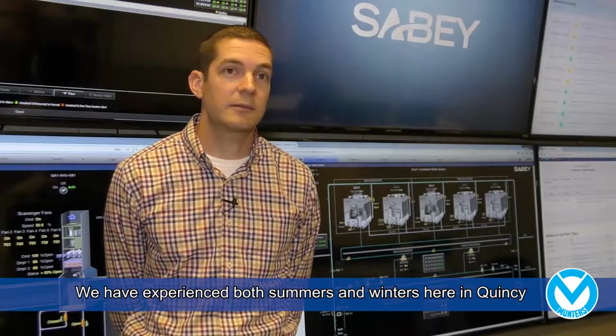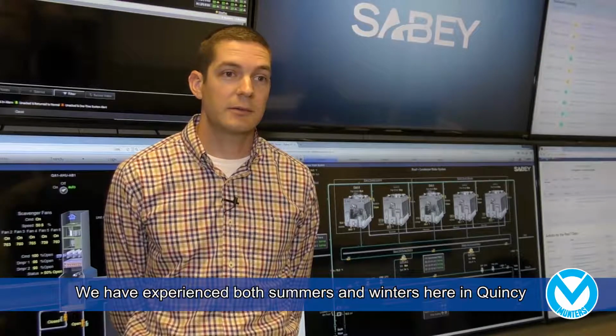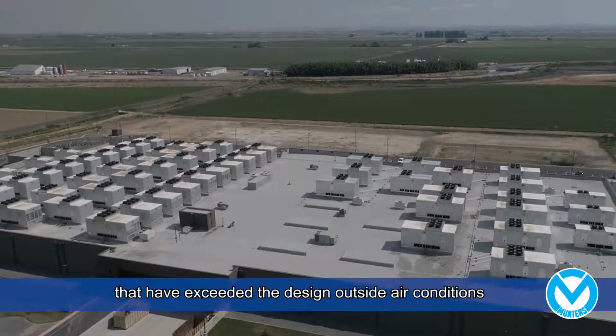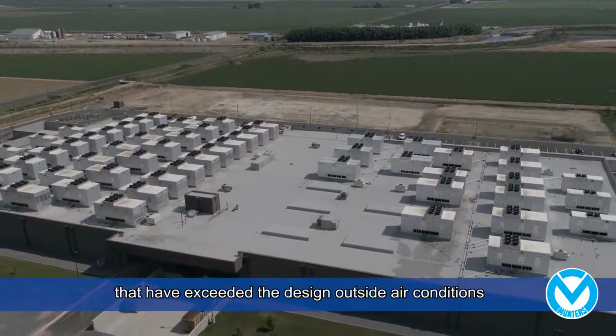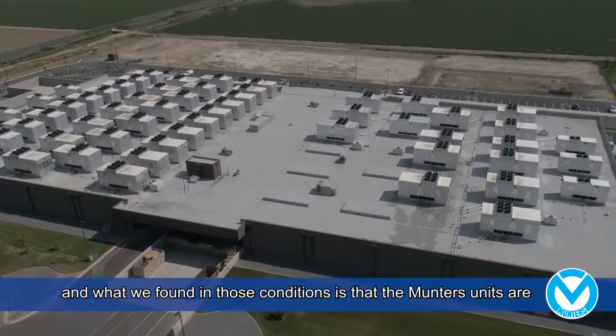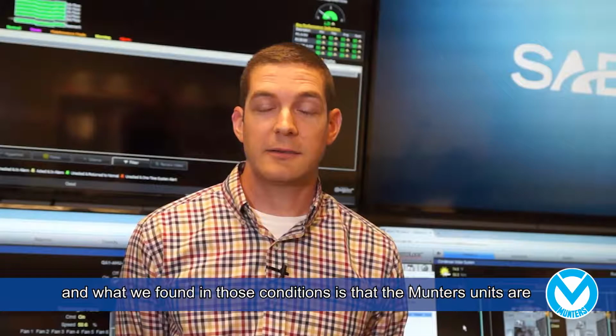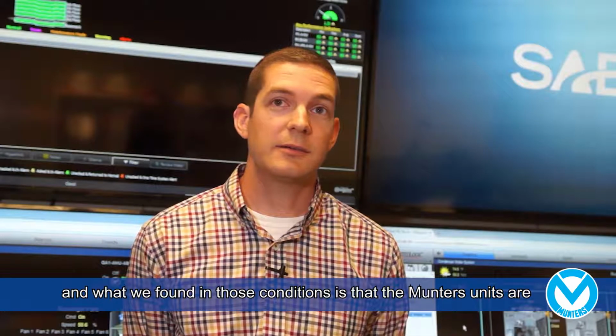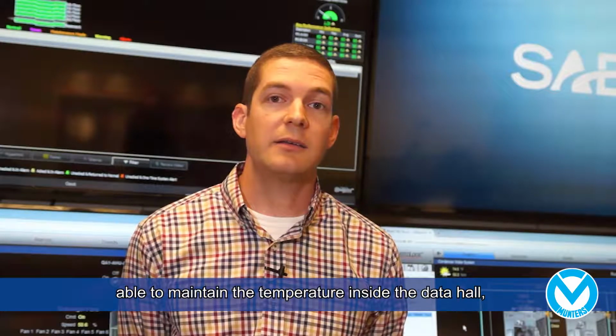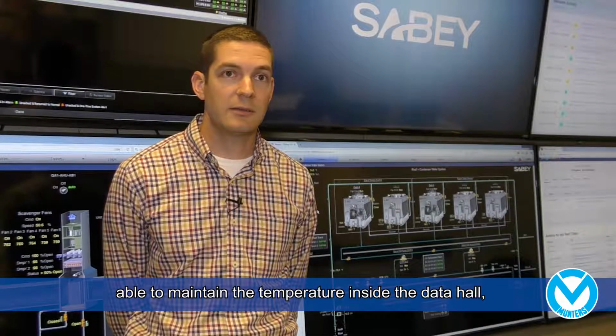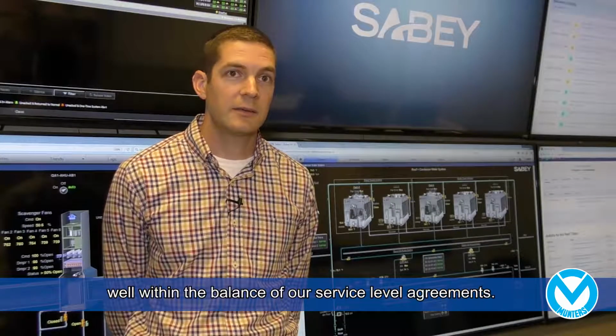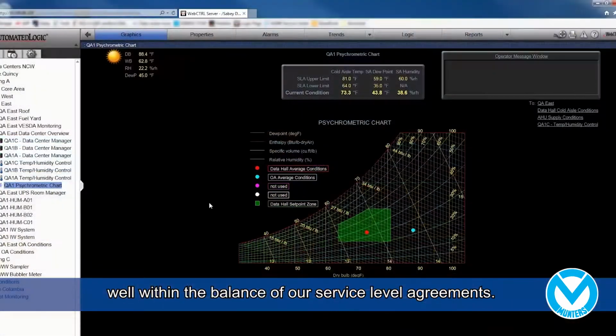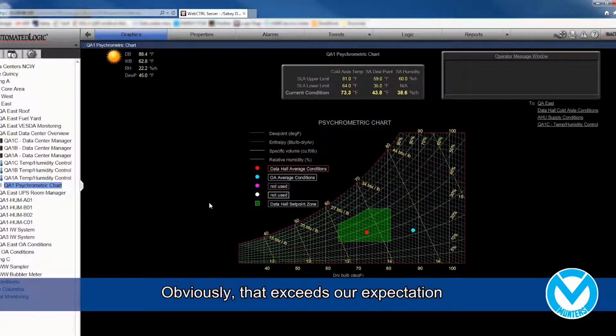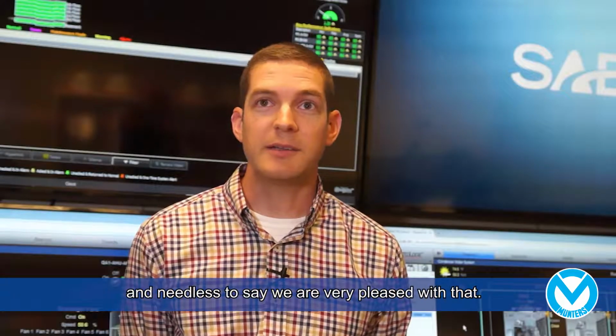We have experienced both summers and winters here in Quincy that have exceeded the design outside air conditions. And what we found in those conditions is that the Munters units are able to maintain the temperature inside the data hall well within the bounds of our service level agreements. Obviously, that exceeds our expectations, and needless to say, we're very pleased with that.